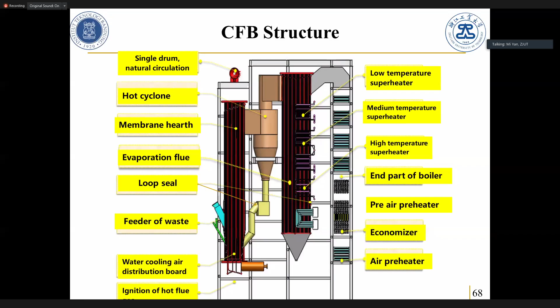So you are right, you are very familiar with coal power plant. This is the reason why we design like this. Two reasons: first, if we say this is the chamber, this is the first flow channel. The flue gas leaves the furnace, comes here, then goes down, then goes up. The superheater is here, primary air is here. We can increase the flow channel, so we can increase the residence time for flue gas, which is helpful for completely burning the organic components in the flue gas. This gives longer time combustion and reduces CO and incomplete combustion products.